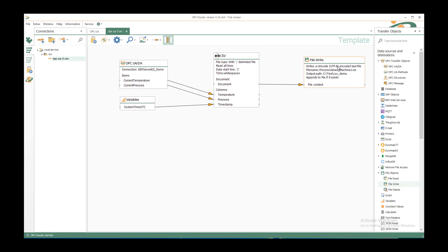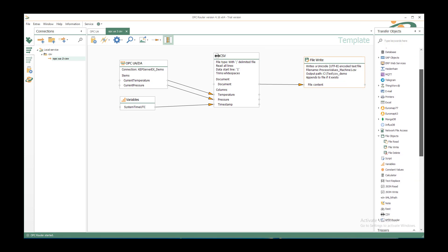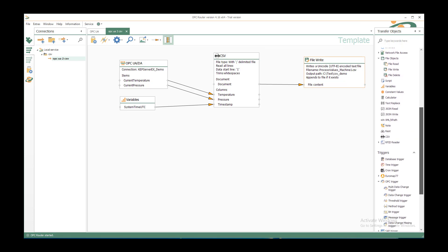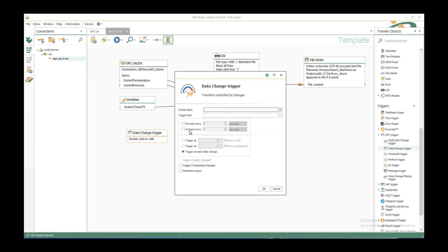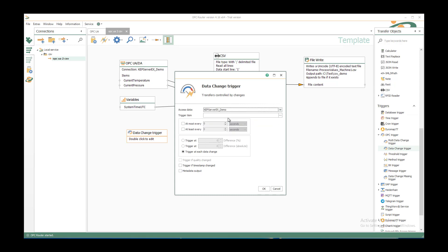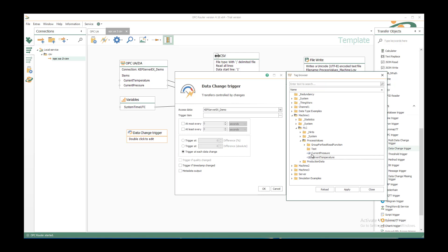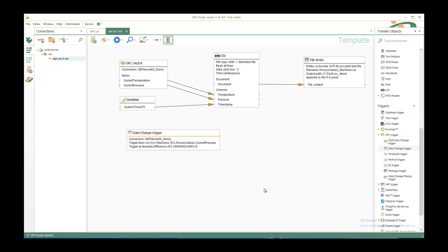This is everything for the connection. Now we still need to say when to trigger. Therefore we have the triggers part. And under OPC trigger we just use the data change trigger. Just double click to edit and we can say we want to select the KEPServerEX OPC server as before. And a trigger item we want to select the current pressure. Every time the current pressure changes about 0.1 difference, because it's a floating point, we don't use a trigger at each data change for this type normally. So we can say OK.